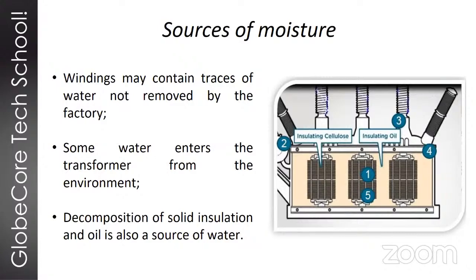The second source, probably the most common one, is the atmospheric water from the air. So every time we have a problem with the tightness of the transformer, there is a leak of some sort, water from the atmosphere comes in. And this is because transformers heat and cool down periodically. So when the temperature increases and when it drops, due to thermal expansion and contraction, what happens is a process that really resembles breathing. So the transformer intakes atmospheric air and obviously takes in water from that air. And this water from the atmosphere goes into the transformer and it becomes part of the oil or the paper. And this obviously is something we really don't want to happen.